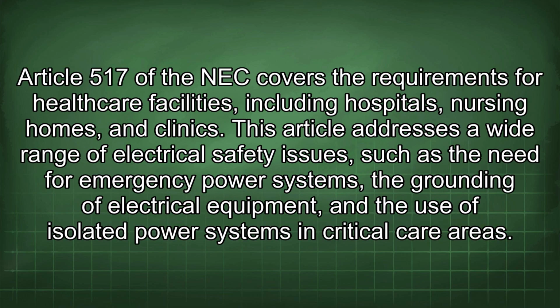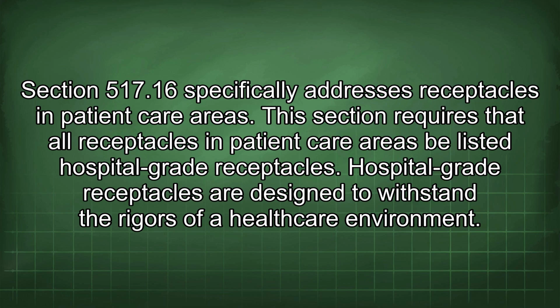Article 517 of the NEC covers the requirements for healthcare facilities, including hospitals, nursing homes, and clinics. This article addresses a wide range of electrical safety issues, such as the need for emergency power systems, the grounding of electrical equipment, and the use of isolated power systems in critical care areas. Section 517.16 specifically addresses receptacles in patient care areas.